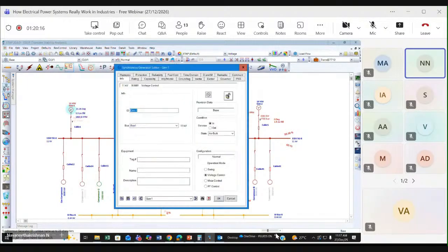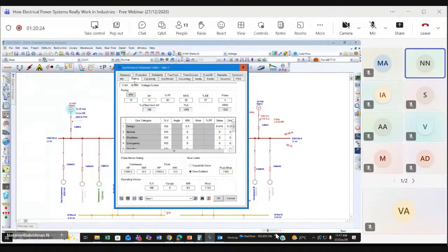I will show some demo here. The generators' information is already filled in. For example, generator 1, and the ratings are mentioned here: 16 megawatt, 11 kV, operating power factor 80%. That is 20 MVA based on 80% power factor, 97% efficiency. It's a 4-pole generator, an 11 kV generator. The connected load maximum is 9.5 megawatt, and Qmax is given here. The operating point value is also mentioned here, 9.5 megawatt.